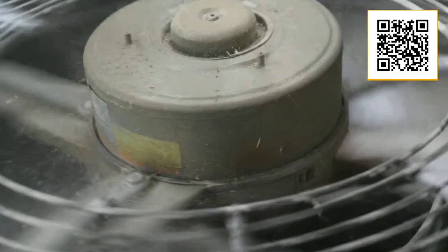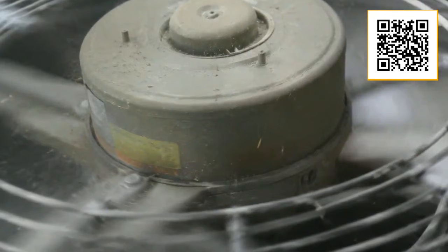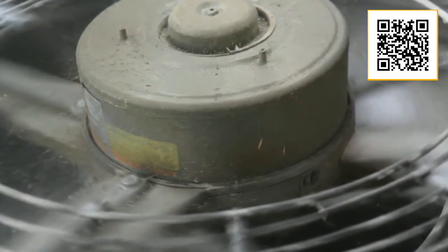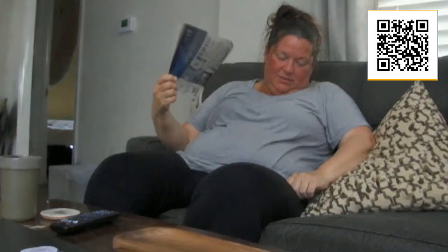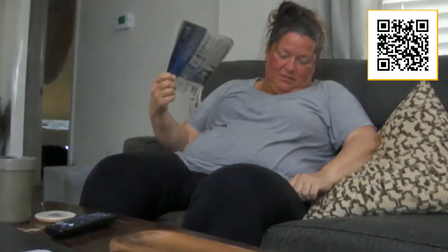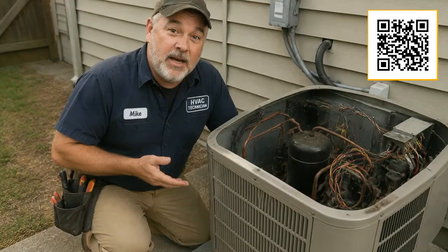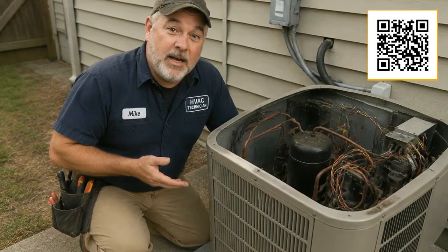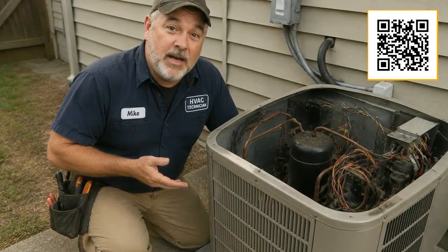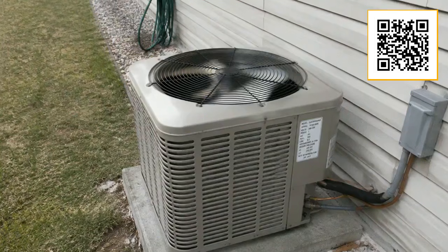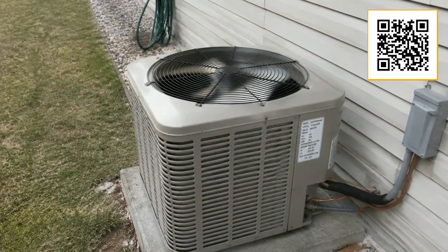When a unit is too large for the space it is cooling, it short cycles. It kicks on, cools the air down fast, and shuts off before it has had time to properly dehumidify the home. You end up with a house that feels cool but clammy. And the constant starting and stopping puts enormous strain on the compressor, which is the most expensive component in the entire system. The compressor is not designed to be cycled on and off dozens of times a day. It is designed for longer, steadier runs.